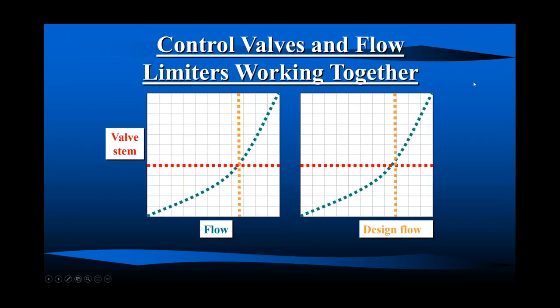How so? Well, let's take a look. This is our valve stem. Here's our flow. This yellow line is our design flow, our design day flow. This is going to be a modulating control valve on a terminal unit. So control valves and flow limiters working together, right? Misconception that they fight each other. Nope, it's a flow limiter. The control valve always has authority. So a modulating control valve opening, modulating to the temperature in the space, perhaps.